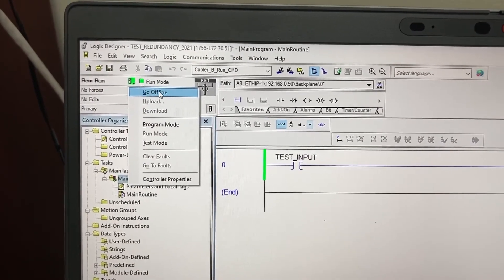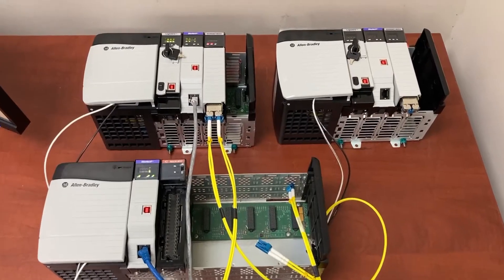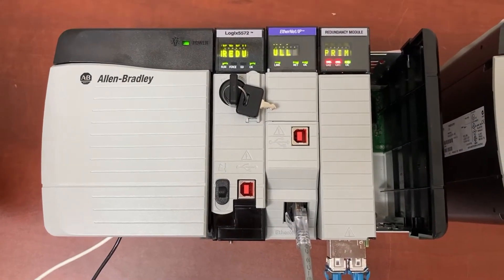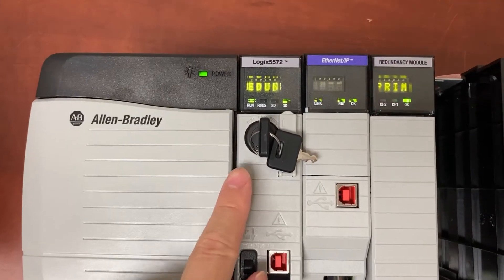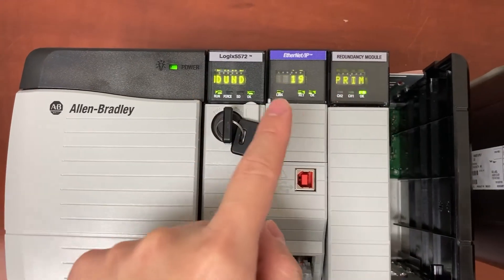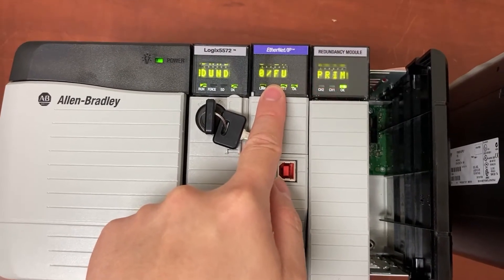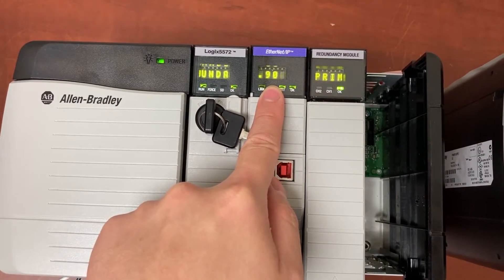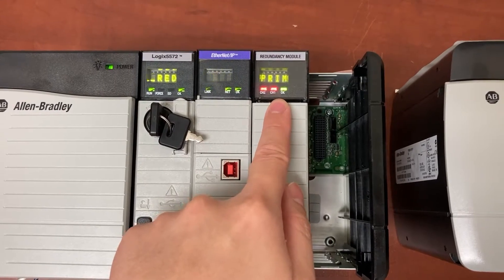Go offline. The program was successfully downloaded to the first PLC rack. We can see the project name displayed on the CPU module, the IP address displayed on the Ethernet module — 192.168.0.90 — and primary displayed on the redundancy module.